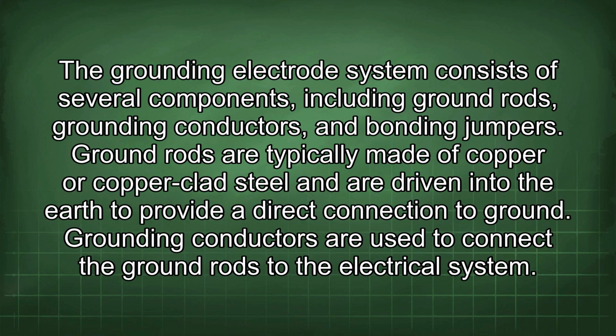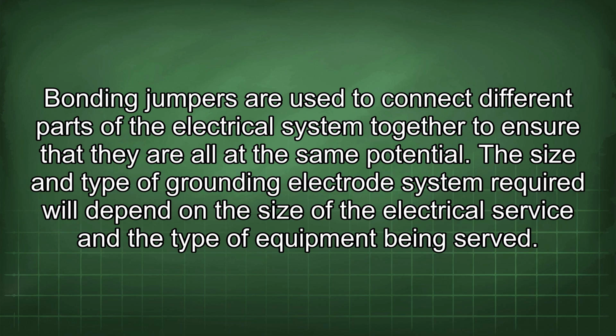The grounding electrode system consists of several components, including ground rods, grounding conductors, and bonding jumpers. Ground rods are typically made of copper or copper-clad steel and are driven into the earth to provide a direct connection to ground. Grounding conductors are used to connect the ground rods to the electrical system. Bonding jumpers are used to connect different parts of the electrical system together to ensure that they are all at the same potential. The size and type of grounding electrode system required will depend on the size of the electrical service and the type of equipment being served.